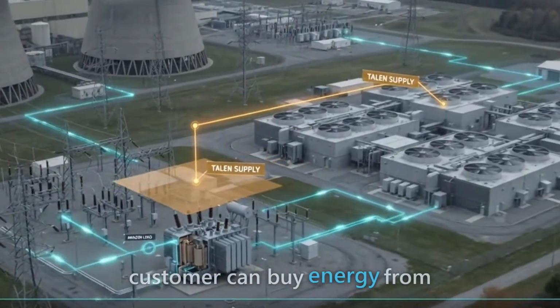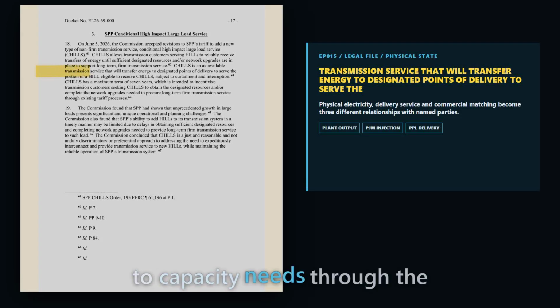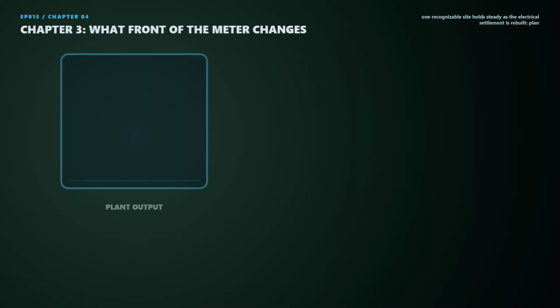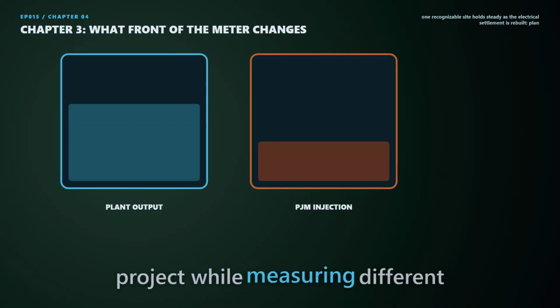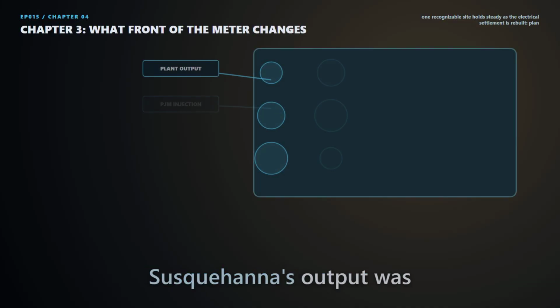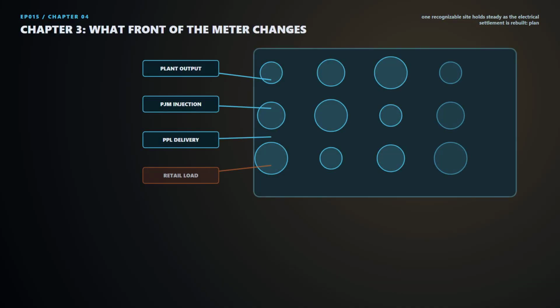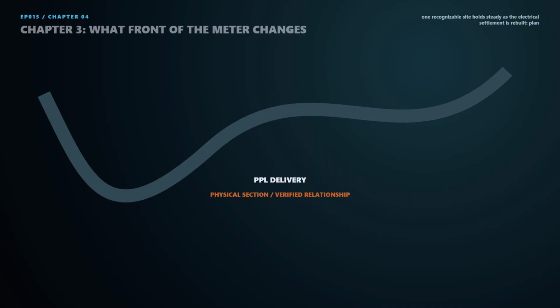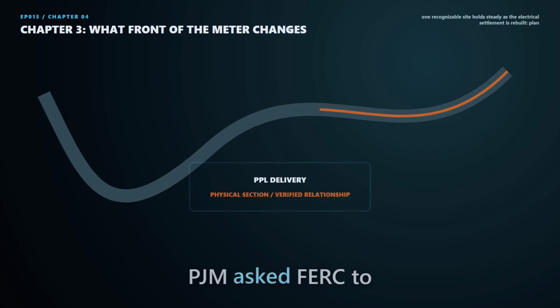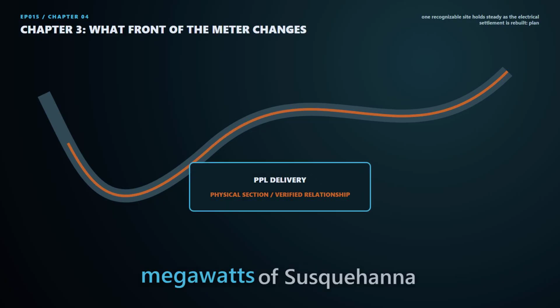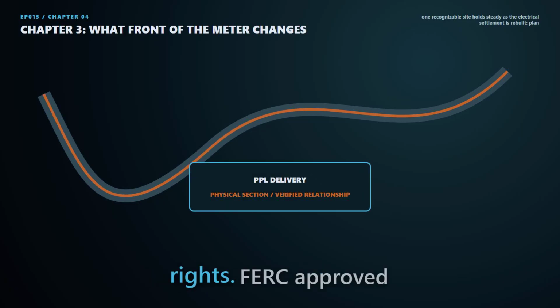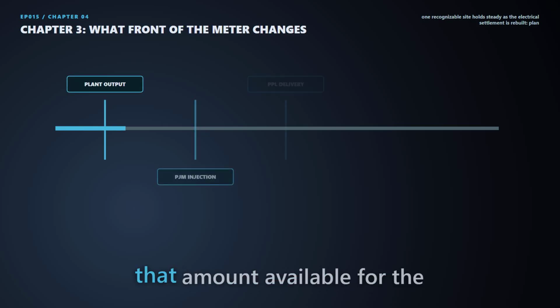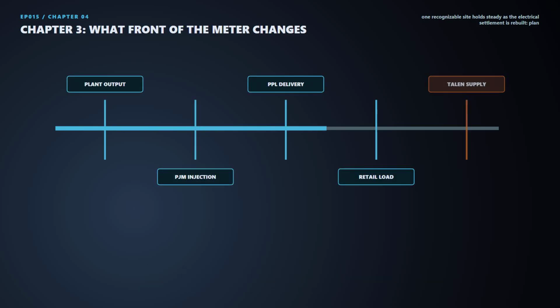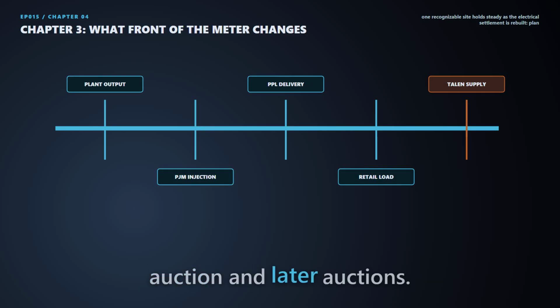A customer can buy energy from one plant, contribute to capacity needs through the regional market, and reserve transmission delivery from a utility. Those payments can appear together on the same project while measuring different services. When part of Susquehanna's output was committed behind the meter, PJM did not count all of that generation as available to the capacity market. After the load entered the forecast, PJM asked FERC to restore 148 megawatts of Susquehanna capacity interconnection rights. FERC approved the request, making that amount available for the 2027-2028 capacity auction and later auctions.